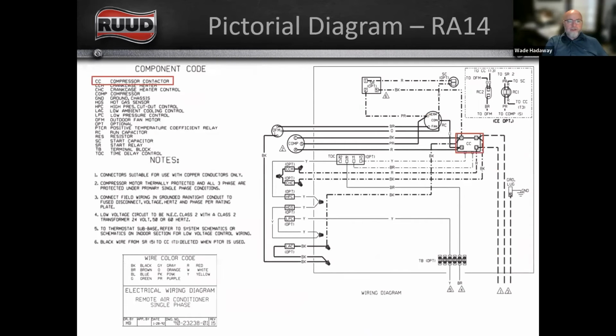Onto our pictorial diagram. So we were just talking about the compressor contactor. There's a red box around the contactor now, and you can see that in this pictorial diagram, we mix both the line voltage and the control voltage. So that's just the difference between a schematic or a ladder and a pictorial diagram. You can see coming out of T3, we have got a red wire going to the run terminal of our compressor. We have got a black going to common, and then we have got an orange wire also coming out of T1 going to the common terminal on our capacitor.